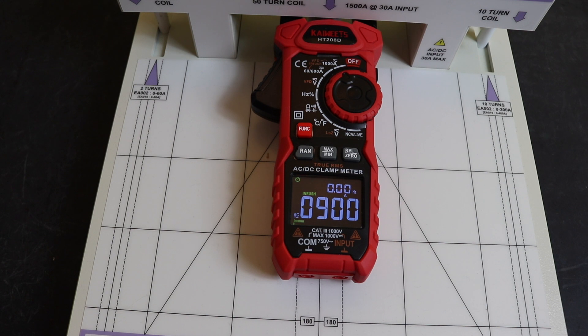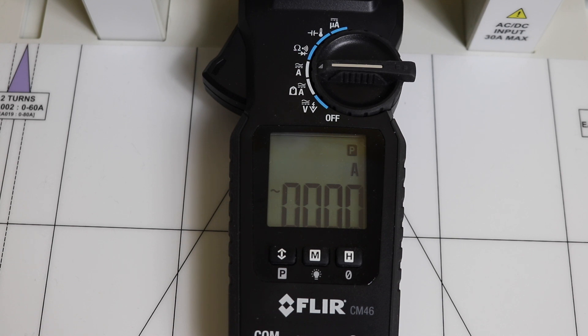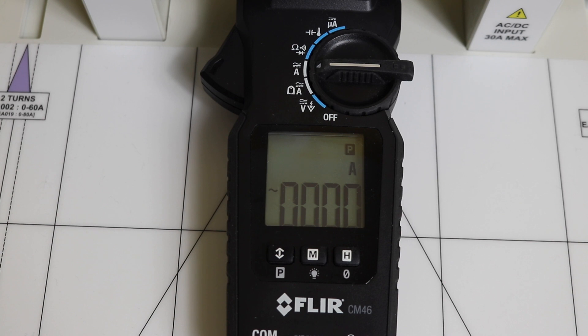Moving to the FLIR CM46 — this is only a 400 amp clamp, so we won't cover the full range we did with the Kaiweets. For the remaining clamps I've settled on injecting 350 amps AC and DC. On the CM46 at 50 hertz AC we get 353 amps. Converting to DC and resetting, we get 340 amps — not too bad. As I recall, this was one of the better ones in the initial single-turn coil tests.